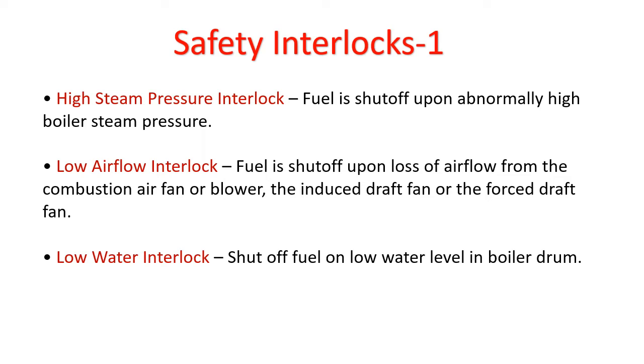Fuel is shut off upon loss of airflow from the combustion air fan or blower, the induced draft fan or the forced draft fan. In case there is low airflow, in the boiler you are basically mixing fuel and air, and that causes the combustion, right? So if the airflow itself becomes less, then what will happen? Your fuel will continue to flow, so there will be accumulation of the fuel inside the boiler and this may cause an explosion. That's why if the airflow is low, the fuel should cut off so that there is no chance of accumulation of fuel, and that's how you can save the boiler.